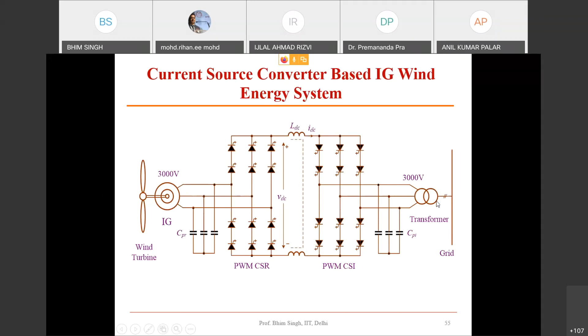Apart from that, these capacitors are not required in case of voltage source converters because the winding inductance here is enough to work as a filter, and on this side the transformer inductance or leakage reactance is enough to work as a filter. So the control is simple.